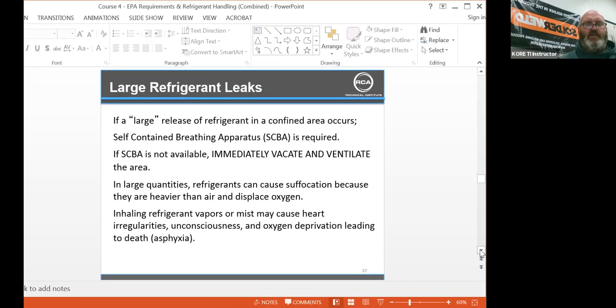If a large release of refrigerant in a confined area occurs, self-contained breathing apparatus is required. If SCBA is not available, immediately vacate and ventilate the area. In large quantities, refrigerants can cause suffocation because they are heavier than air and displace oxygen. Inhaling refrigerants or mist may cause heart irregularities, unconsciousness, and oxygen deprivation, leading to death.